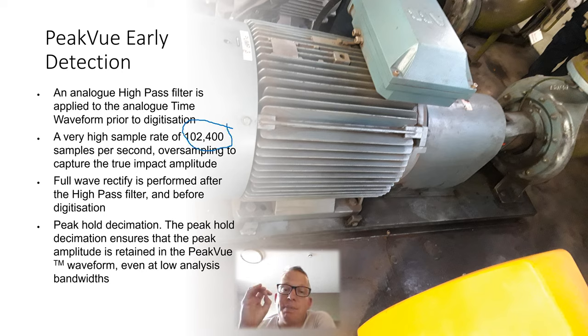So the analyzer is sampling so fast that it's going to capture these very very short transient minute shock pulses from the bearing. Very short pulse, short duration, really high frequency, they're sampling really fast to capture it.